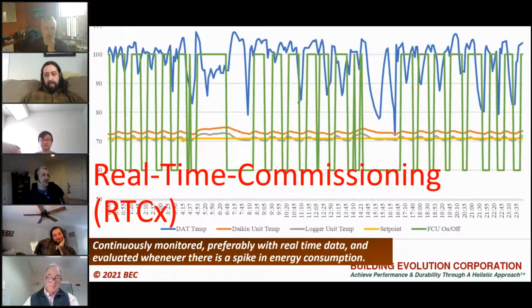This one here is actually temperatures, and what we're monitoring here is when the temperatures get too low in heating, when the fan is on but the temperature coming off that fan coil is getting too low. This person is complaining, I feel cold drafts at nighttime when I'm sleeping. So we're able to monitor when it is happening, and try to put the pieces of the puzzle together as to why this keeps occurring with this particular system. Try to come up with modifications to the controls.